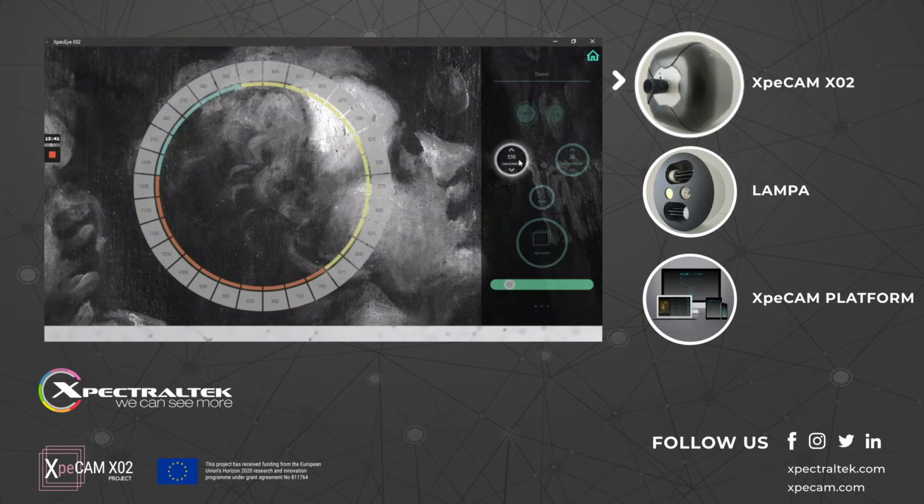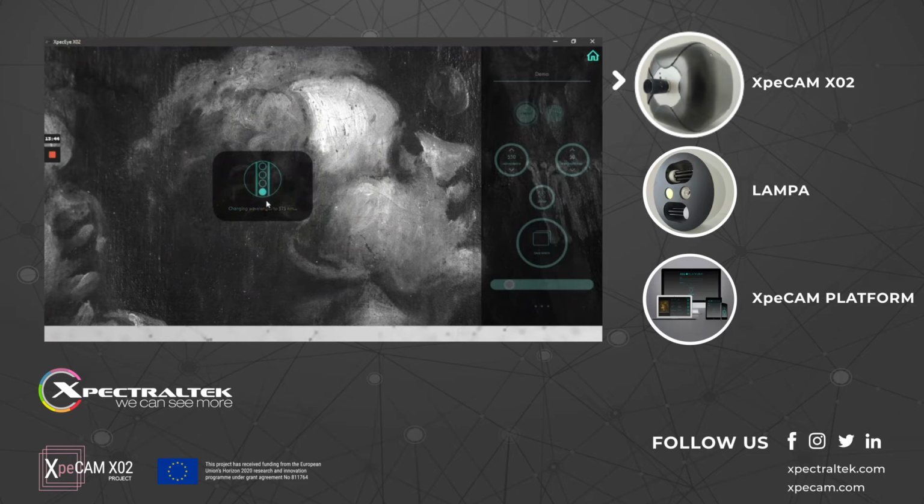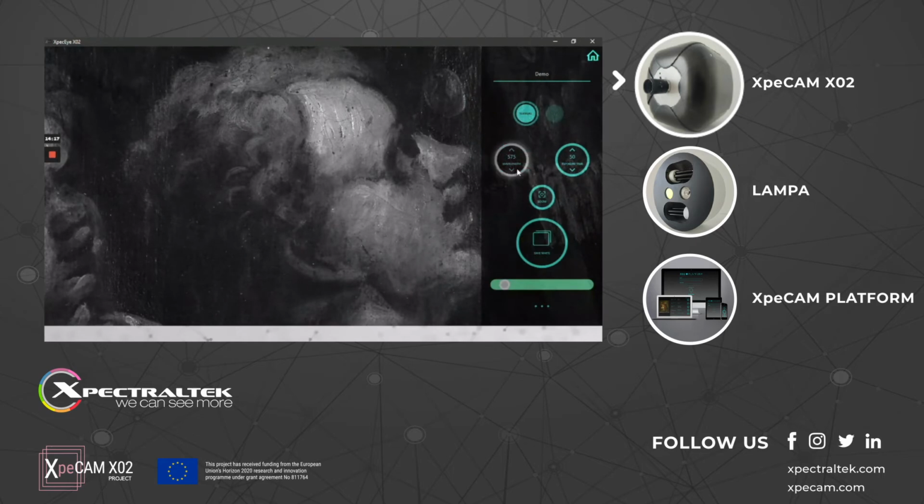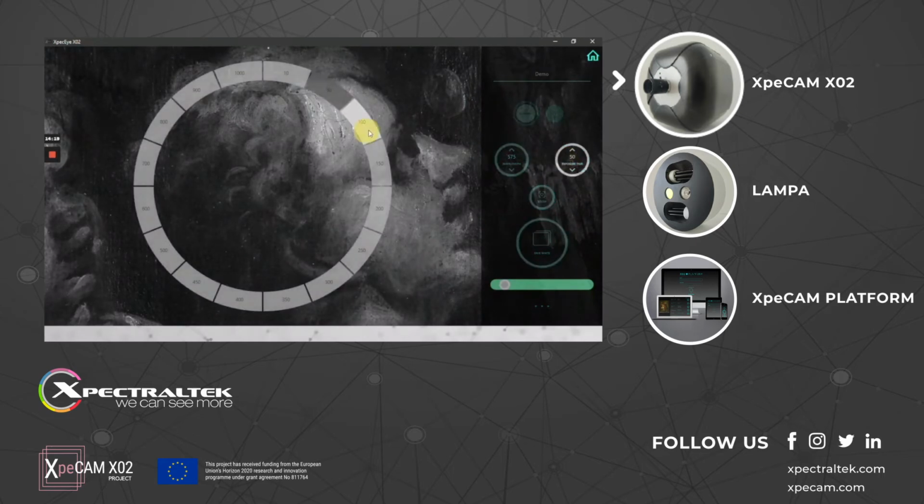After I choose a precise wavelength here, the camera will show me this small square telling me that it is turning on the filters. These filters are physical filters, nothing digital. We have a real filter wheel filled with round filters inside the camera, and it turns to change the wavelengths. Now I will touch the camera and work with the diaphragm, and here on the side I can work with the exposure time.